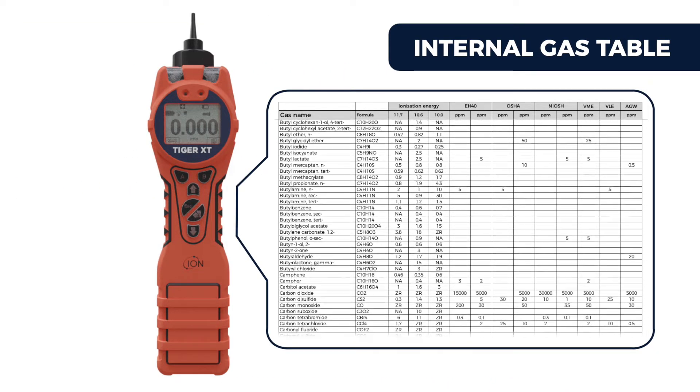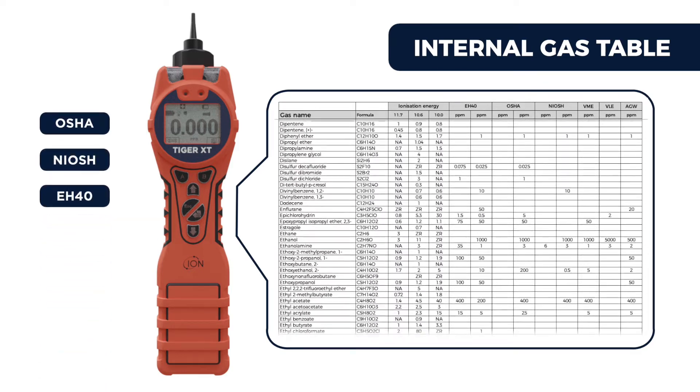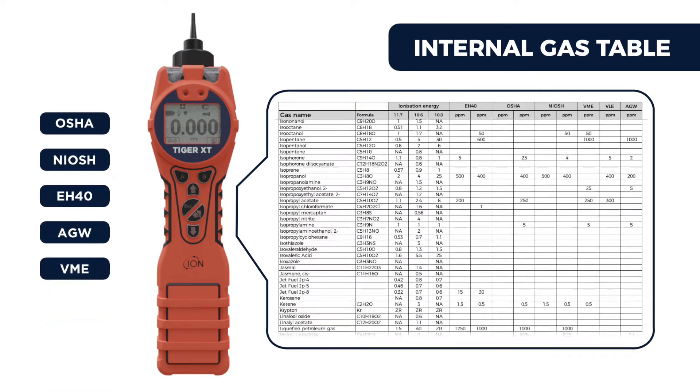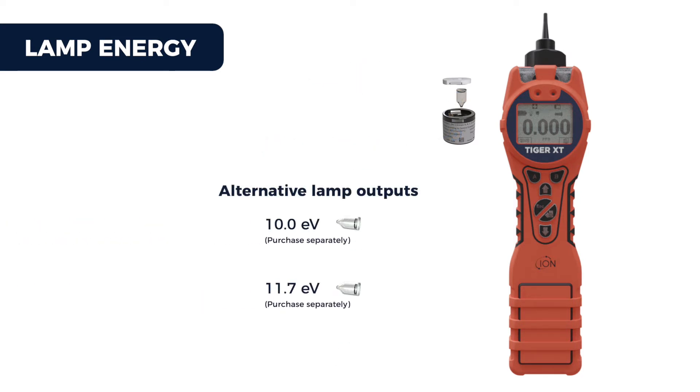Tiger XT has an internal gas table with hundreds of response factors and work exposure levels from OSHA, NIOSH, EH40, AGW, and VME. Tiger XT is supplied with a 10.6 eV lamp so can detect many hundreds of VOC gases. 10.0 and 11.7 eV lamps are also available.